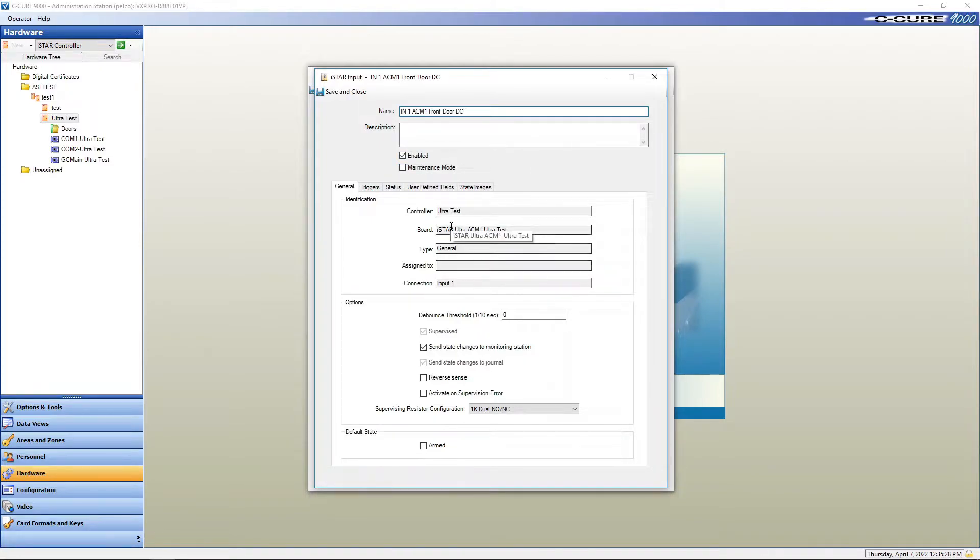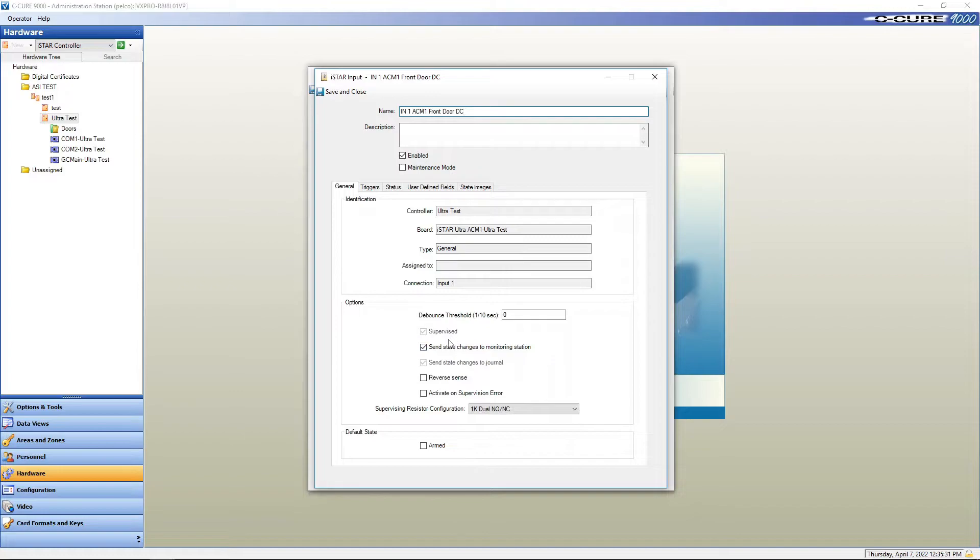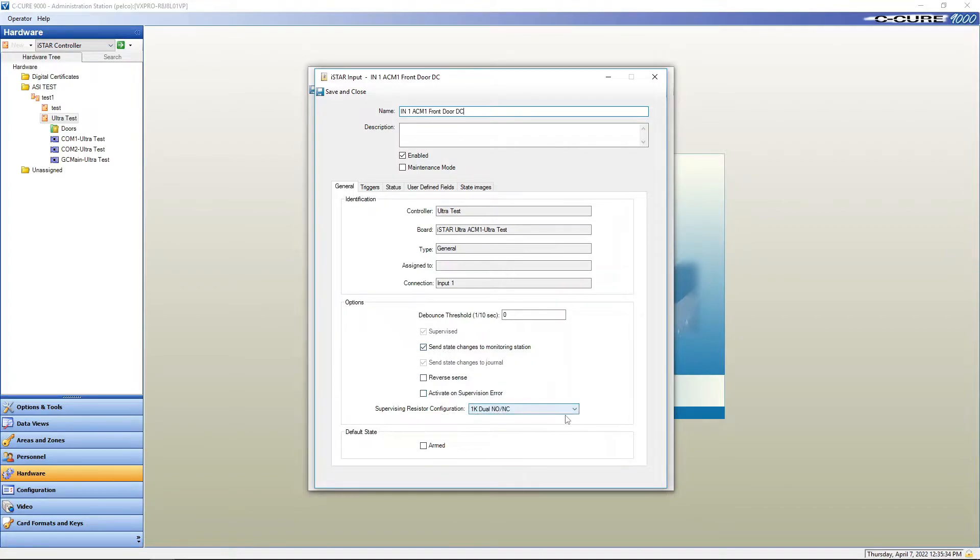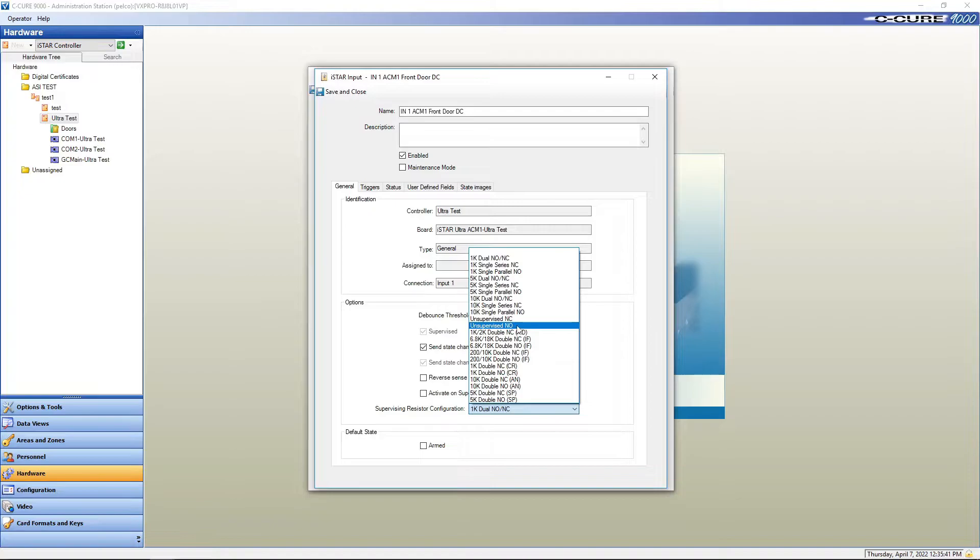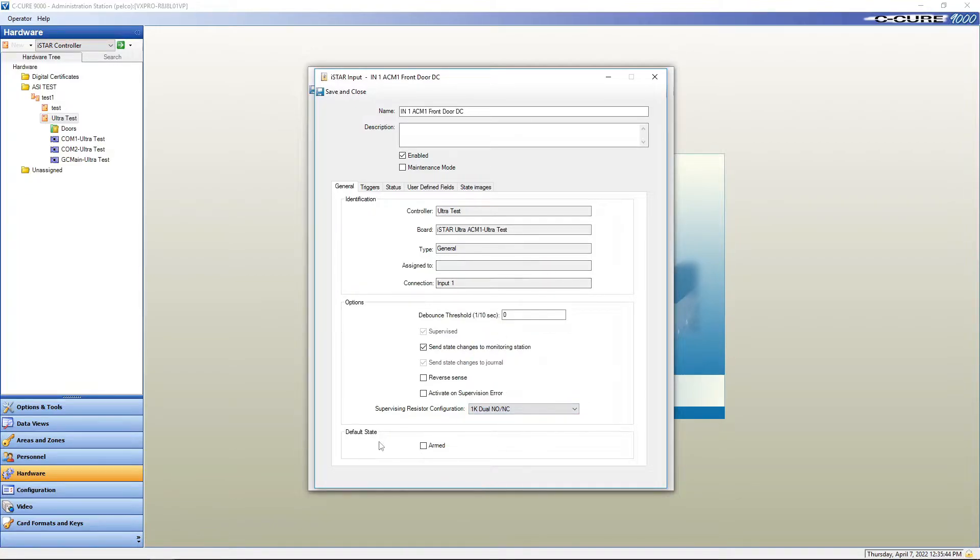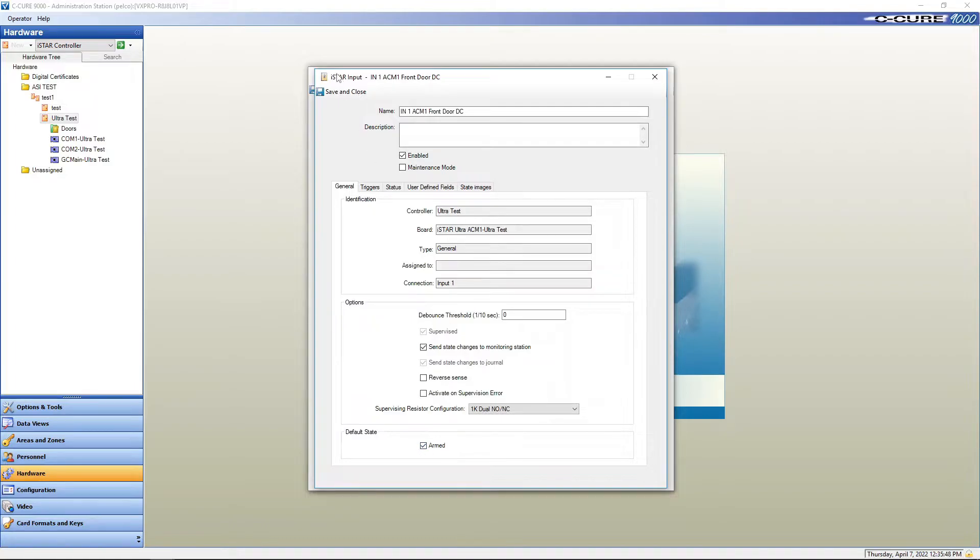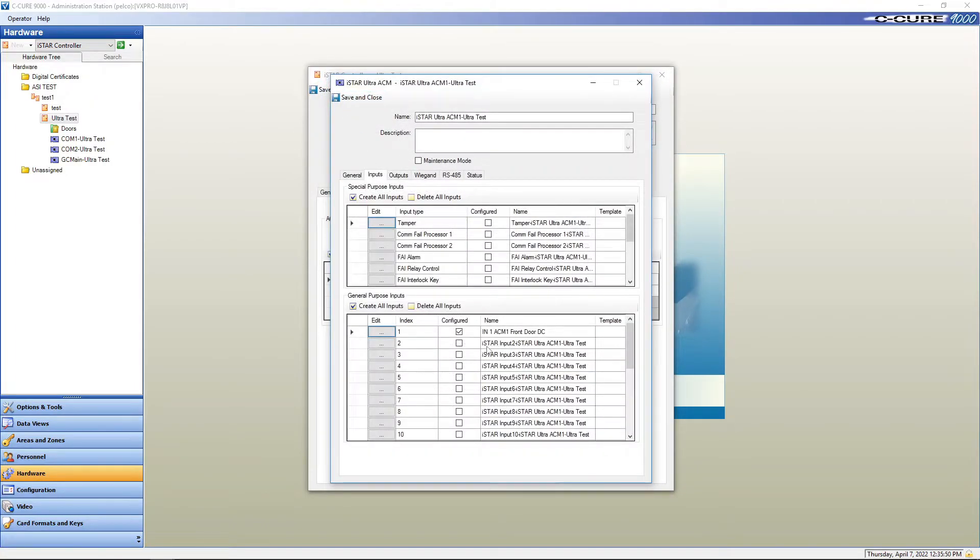Make sure that it's enabled. This is all of your relative programming information. And then, of course, the resistor that's hooked up to it, or you can set it up for unsupervised or supervised. And then you have to arm it in order for it to work. Save and close.